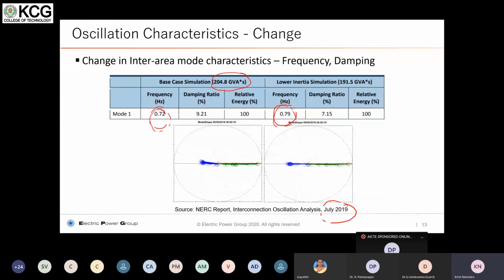For example, if the disturbance that has happened had a frequency of 0.72 hertz, it would have caused an inter-area resonance here. Now, since the inter-area resonance has moved because of the non-inertial support to 0.79, now a 0.79 hertz disturbance can cause inter-area oscillation, which is very dangerous, because under resonance conditions, the value of the megawatts that flows in the tie lines can go up by a factor of the quality factor, which depends on the kind of resonance that happens in a system.